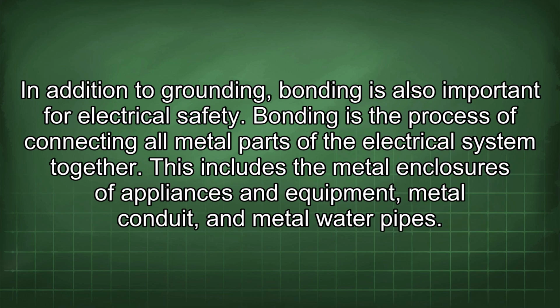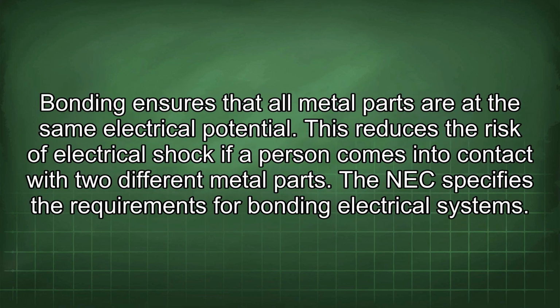In addition to grounding, bonding is also important for electrical safety. Bonding is the process of connecting all metal parts of the electrical system together. This includes the metal enclosures of appliances and equipment, metal conduit, and metal water pipes. Bonding ensures that all metal parts are at the same electrical potential. This reduces the risk of electrical shock if a person comes into contact with 2 different metal parts.